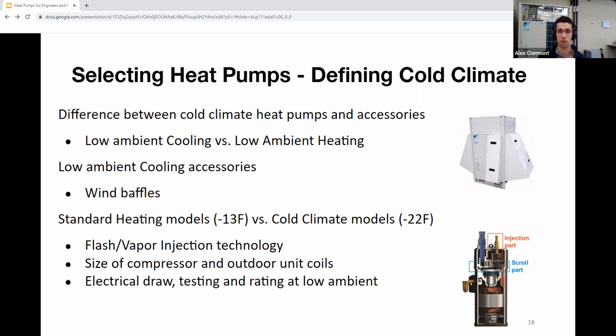So you actually run the risk of overcooling the refrigerant. Now, wind baffles, which is oftentimes a low ambient cooling accessory, helps with that, as it ensures that the cold temperatures of the cold wind do not make this process harder for the machine to do, and do not cause a refrigerant to come inside the building too cold. Sometimes wind baffles are also used to help with heating as well, as they do help with defrost cycles, which we'll talk about in a little bit. But essentially, the machine has to go into defrost, and wind baffles do help with that as well.